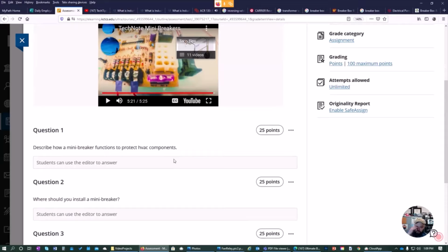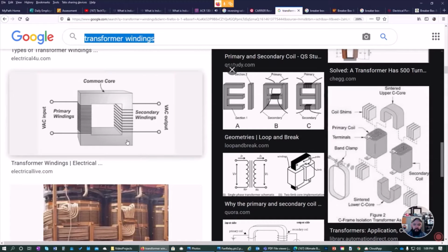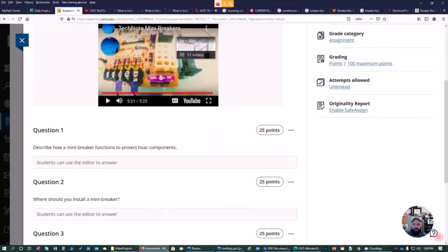That's very simple. A mini breaker will break the hot leg in a transformer. So you have main power coming in, say 120 or 240, and then you have common and hot 24 volts leaving. You would just place the mini breaker in the hot leg. You'll cut this wire, and one side will go into the breaker and pass through and go to the other. It's fairly simple. You want to put it right after the source of the control voltage, which is the hot leg in the transformer. Some, however, have a fuse holder on the circuit board.